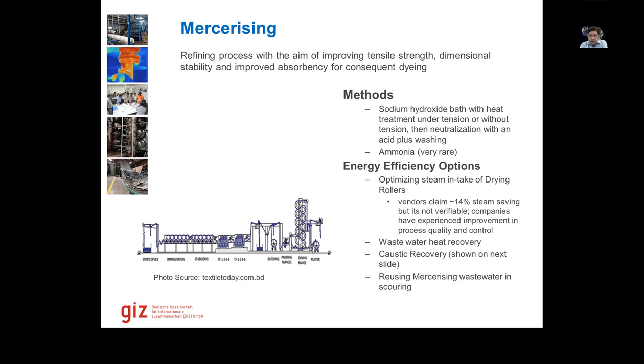Steam goes in and comes out as condensate. In older machines there's no control; you can either switch the steam on or off. But if we have a moisture sensor at the end of these drum rollers, or in the middle of the process, we can optimize by giving a feedback loop to the solenoid valves of the steam drum rollers, and then control the steam intake as well. If we control the steam intake, we can reduce a significant amount of steam consumption.